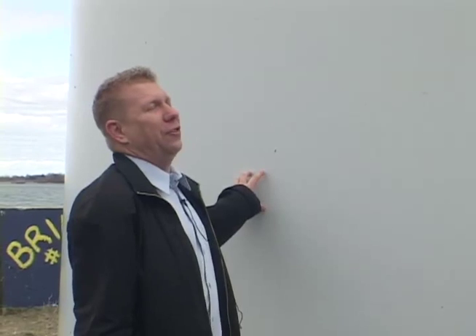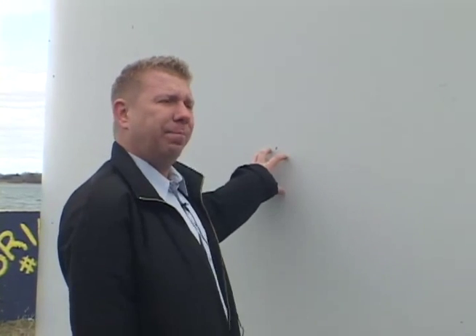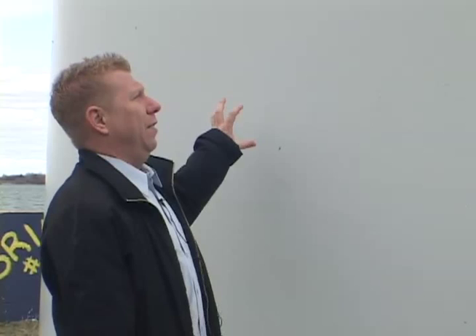So we've had very good luck with this machine. Both machines, it's pretty interesting - this is a 660, that's a 1.8, so that's about 2.7 times the production output. This machine was installed in 2001, and that one in '06. To date this one's done about 11,000 megawatt hours, and that other machine is soon going to eclipse 11,000, so they're going to cross each other on the graph, and that guy is going to be ahead. It's a constant RPM machine, so it always rotates at 28.5 RPM.